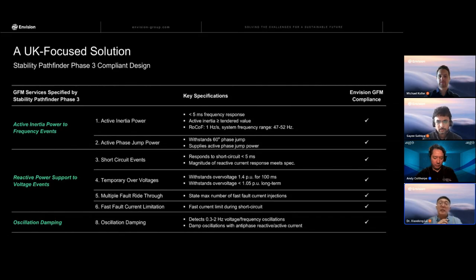Even in the Stability Pathfinder Phase 3, it listed all the detailed test cases on the stability of the grid forming specifications. Here is what I summarized from the Phase 3 compliance note. I categorized their requirements into 3 categories. The first one is inertia to the rate of change of frequency, and inertia to the phase jump. And the second one is reactive power support to the voltage event. Voltage events include the short circuit event, temporary overvoltage, and multiple events.